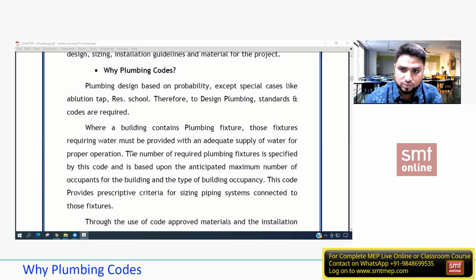So in plumbing, always remember neither undersizing nor oversizing is accepted. If it was firefighting, oversizing is accepted because that's for safety, so that's a different scenario. But in plumbing, we need what is required, because we need to maintain the Q and the velocity, not decreasing or increasing either.